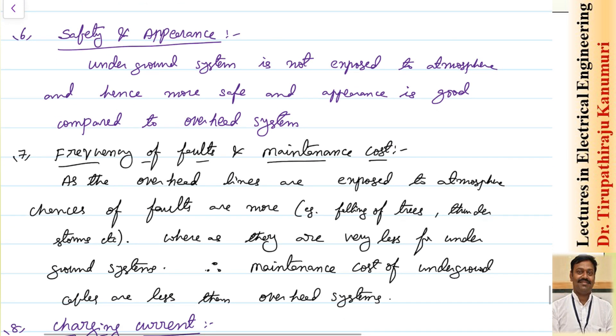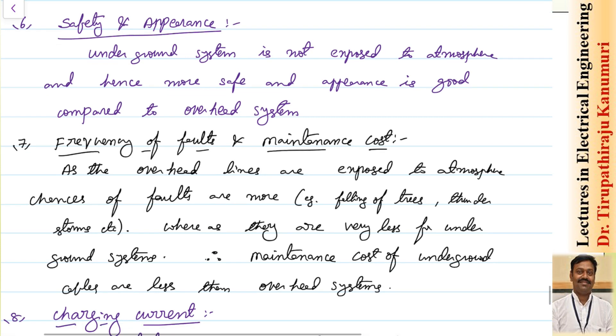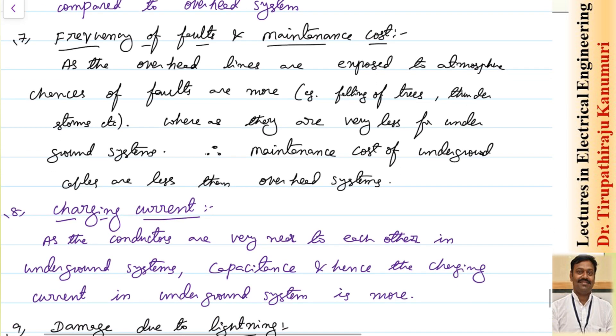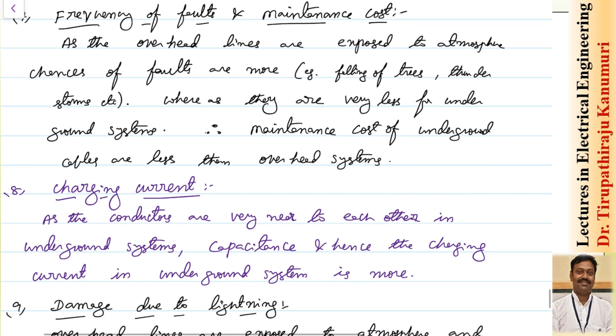Underground systems cannot be used for voltages greater than 66 kV — these are the disadvantages. Coming to advantages: safety and appearance are very good for underground cables, as they are not exposed to the atmosphere. No person will touch them and experience a shock, and appearance is neat. For overhead lines, chances of faults are more due to falling trees, thunderstorms, etc., whereas these are very less in underground systems, so maintenance cost of underground cables is much less.